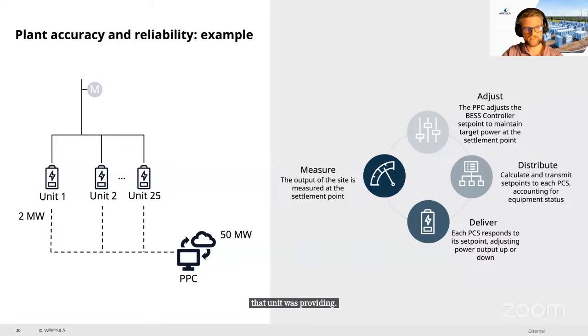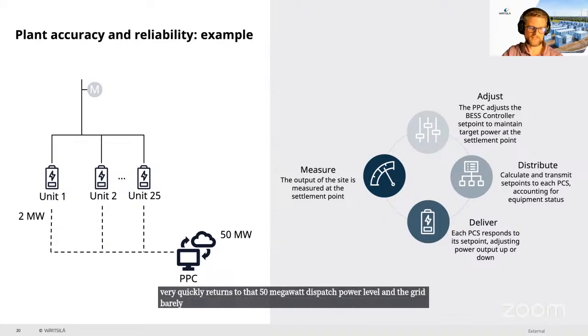In the next iteration of the measure phase of that closed loop controller, it will detect that new 2 megawatt error. So in this case, dropping to 48 megawatts instead of 50 megawatts. So in the adjust phase, the controller increases the demand to the remaining 24 inverters to account for that drop in power. So that as a result, the plant very quickly returns to that 50 megawatt dispatch power level, and the grid barely sees any change. I mean, this is happening so fast that the power just comes right back up almost immediately.